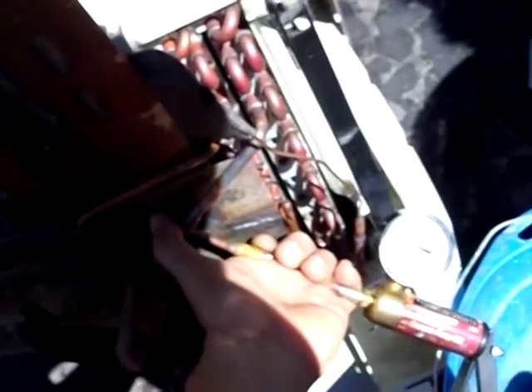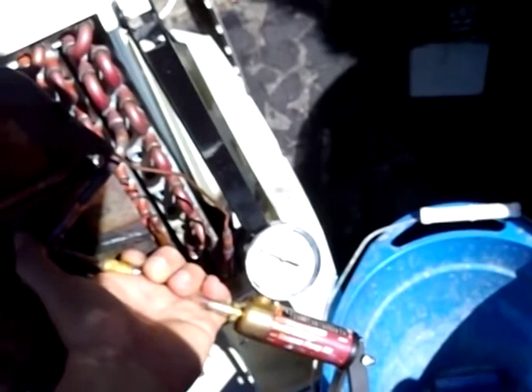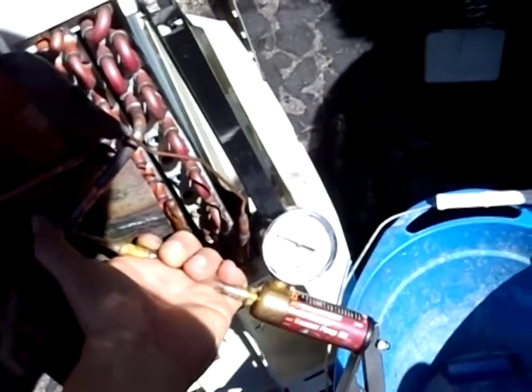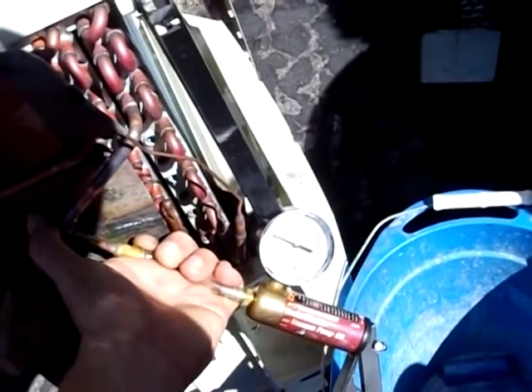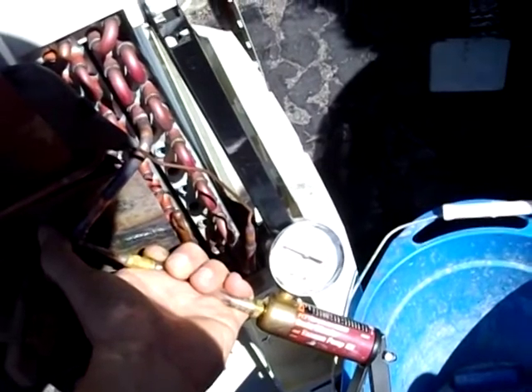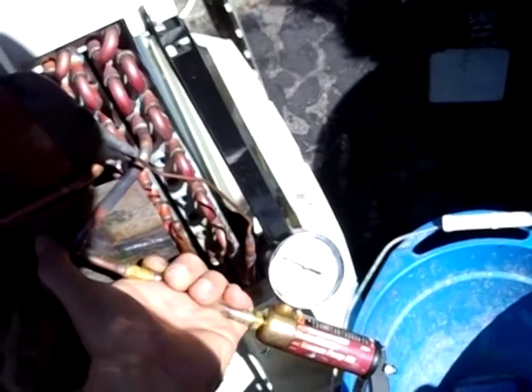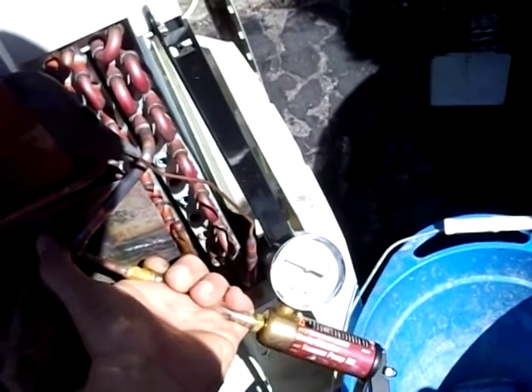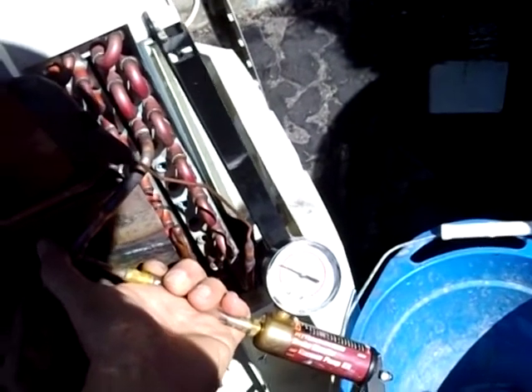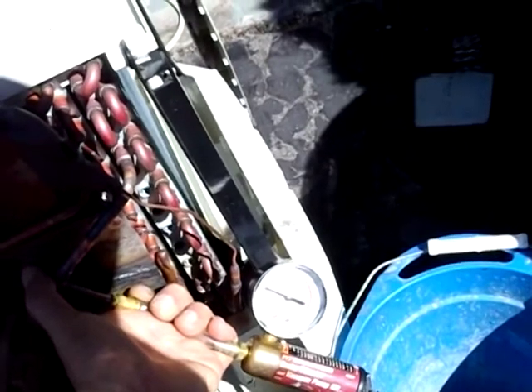Alright, this is the vacuum test right now. I got it to minus 25 inches of mercury, and that needle is steady. When I started off, it might get to say 5, and then it would drop to 4. That's when bubbles are coming out of the oil or whatever, or maybe there's a little moisture in the line, so it's vaporizing, but now it's been stable. But it takes a lot of pumps just to move it 1 inch of mercury. It is steady at 25.